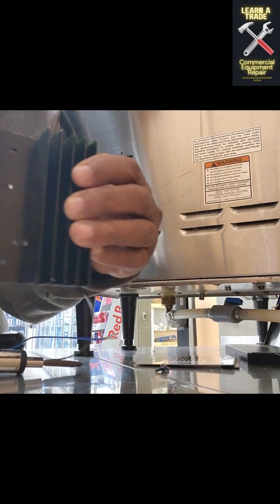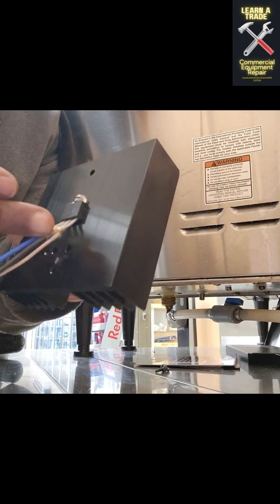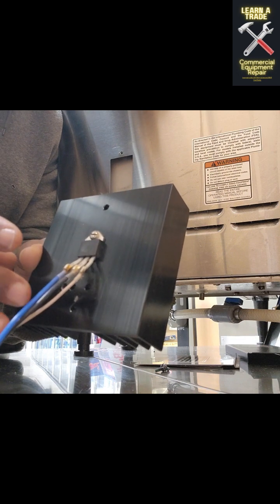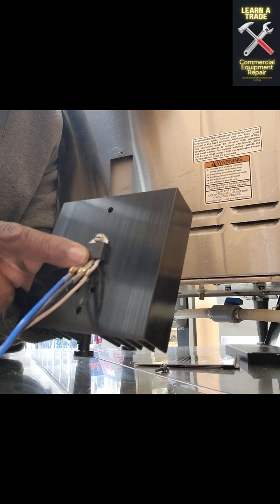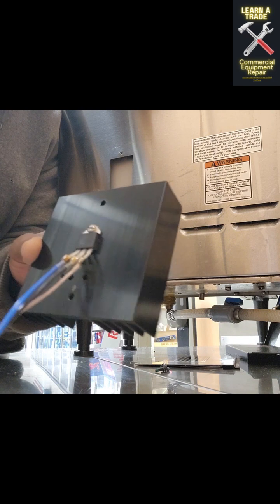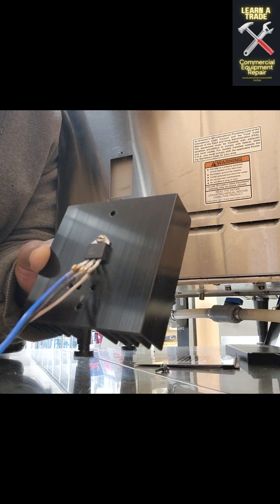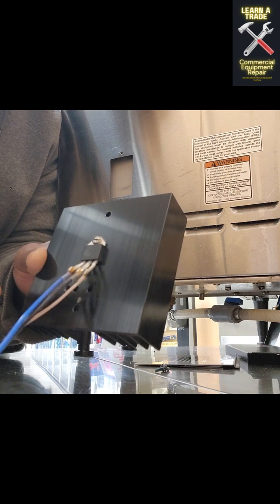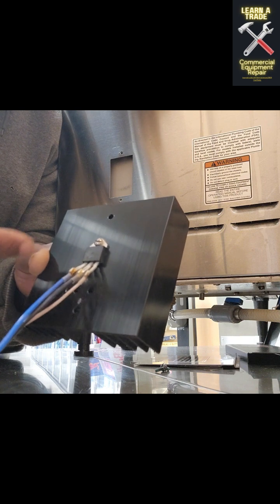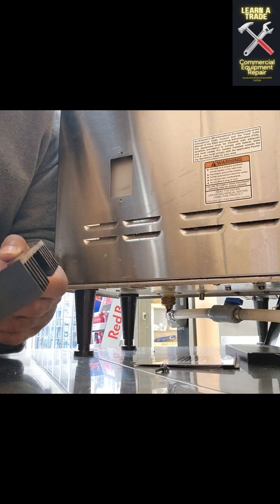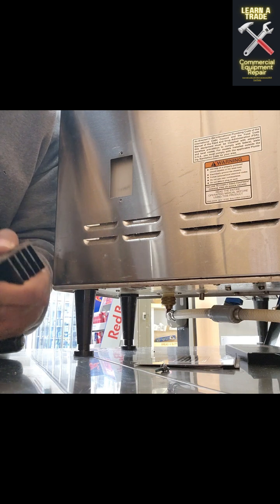Okay, got that out. As you can see, that's the heat sink right there, and this is the Triac. This acts as a sort of electrical switch to shut off the heaters. If the temperature probe malfunctions or doesn't shut it off from the board, these are supposed to kick in to allow those heaters to shut off. So what's happening is it's apparent these aren't kicking in and shutting off the heaters in time, and that causes the machine to boil over, which is not good for the heaters or the board itself.